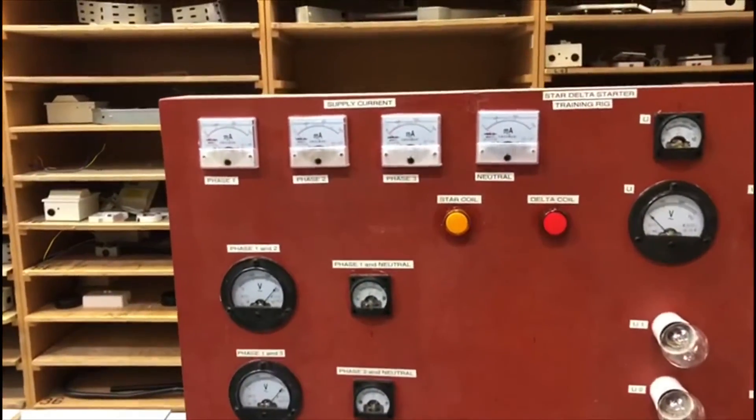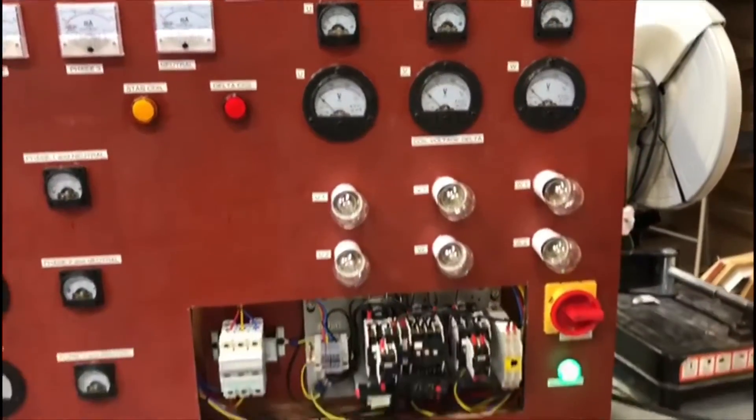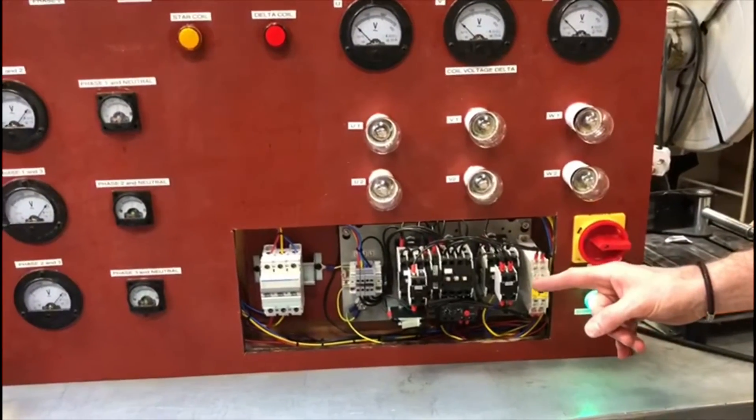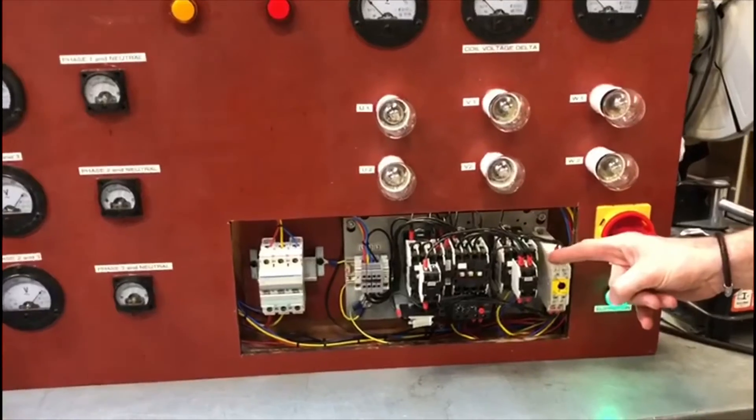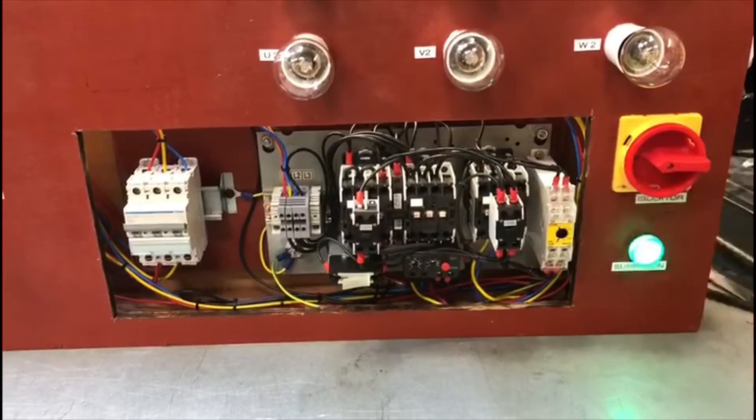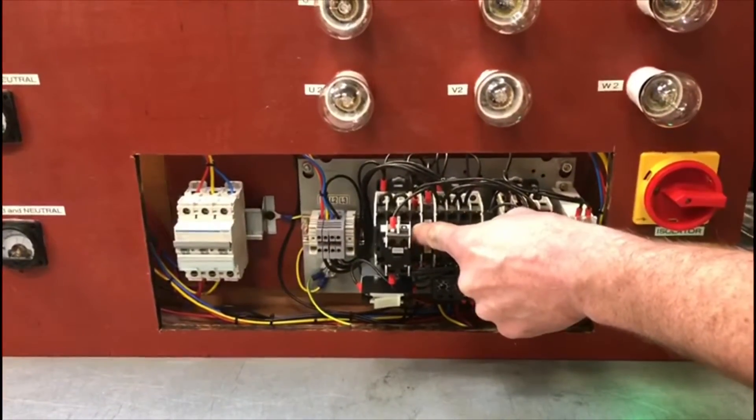We can see that none of the ammeters are working and none of this is working either. So let's just have a quick look at the actual star-delta starter itself. We have the main contactor, okay? So that one always, as soon as you press the on button, the main contactor always pulls in first.